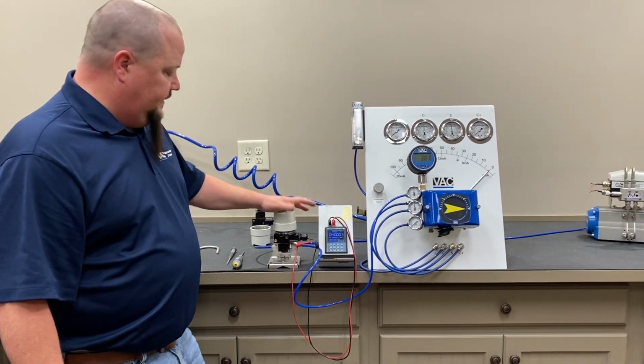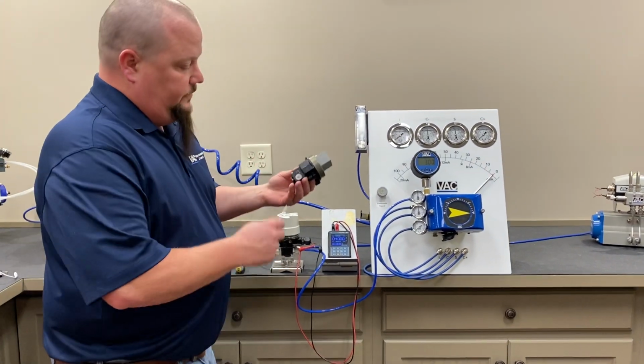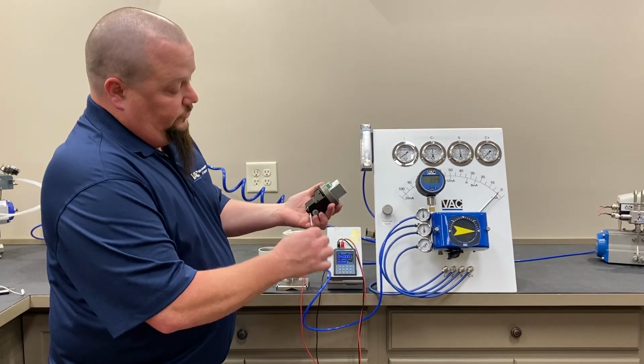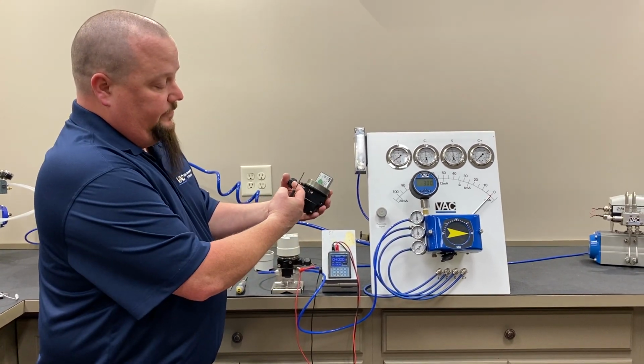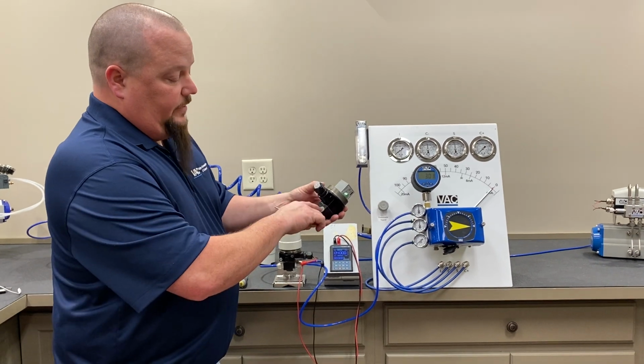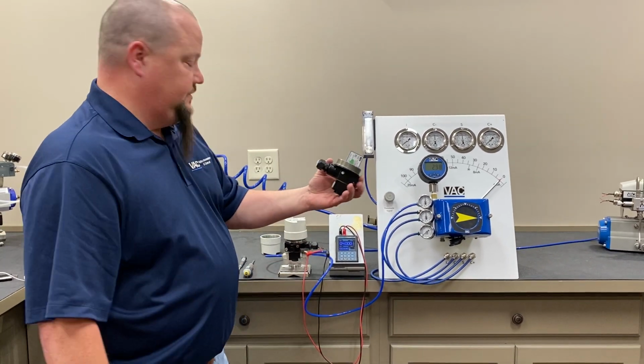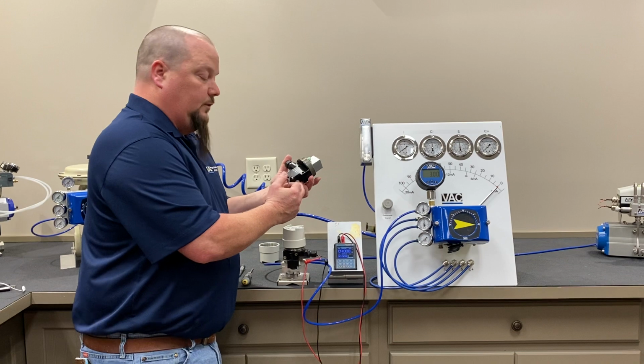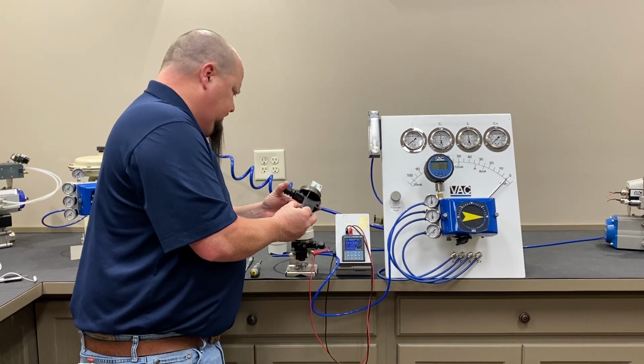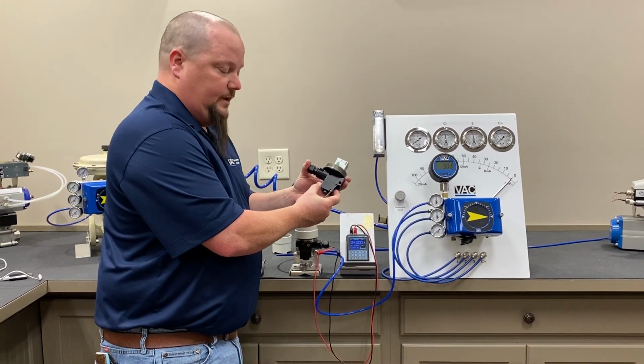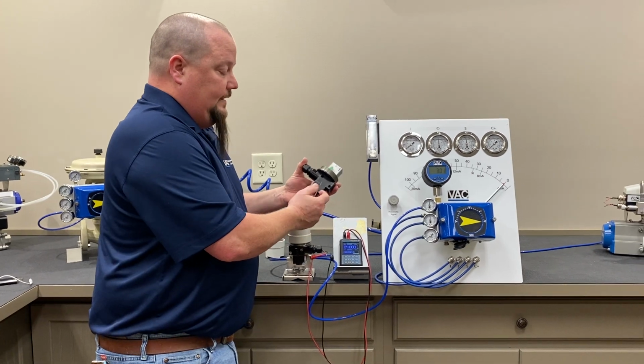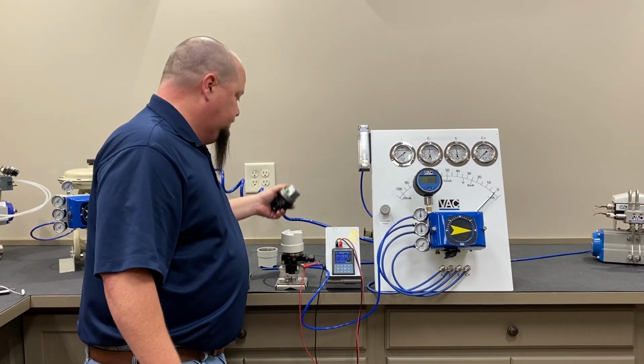I've got the unit set up. There's an inlet and an outlet. So your supply comes in the side opposite of the compression fitting, and your outlet comes out the same side as the compression fitting. So this unit will take anywhere from 20 to 100 PSI, or actually 150 PSI as your supply, and will output 3 to 15.